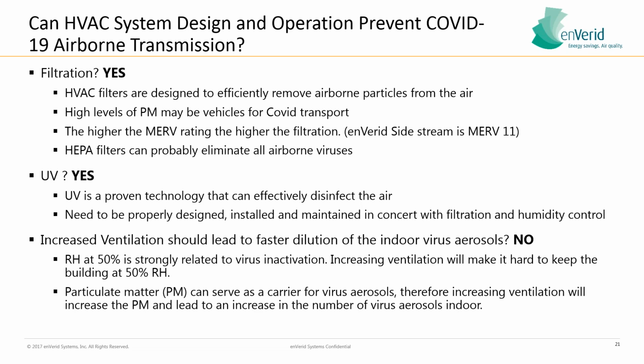And humidity control is actually one of the biggest facets behind controlling COVID-19, as the research is showing, according to this documentation. So, does increased ventilation result in faster dilution of these indoor virus aerosols? The answer is no. Relative humidity at 50% is strongly related to virus inactivation. So increasing ventilation will make it harder to keep a building at 50% relative humidity, meaning that increased ventilation, coupled with the fact that you're bringing in more PM to the building, could actually make the situation worse, according to these studies. So since PM is a carrier for virus aerosols, increasing ventilation might cause a problem.